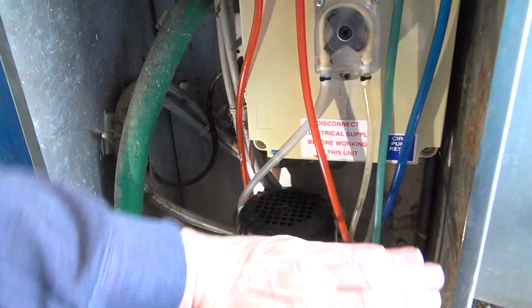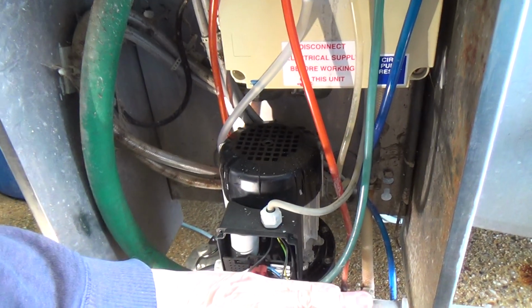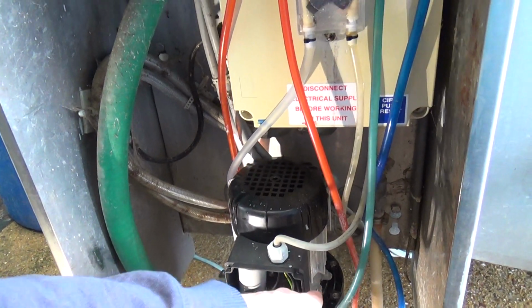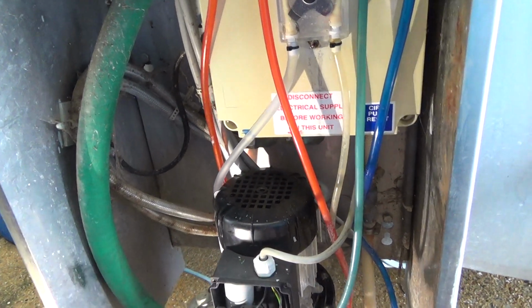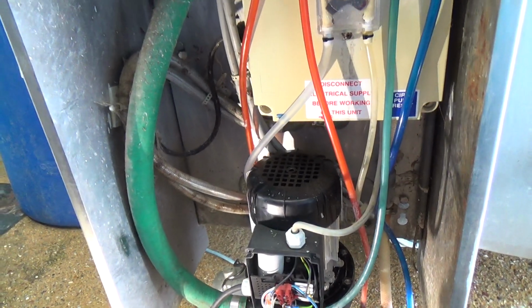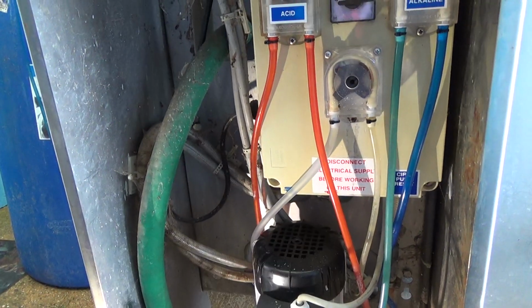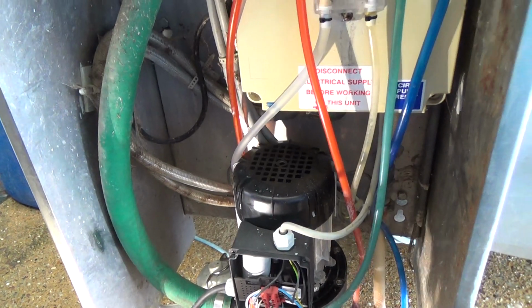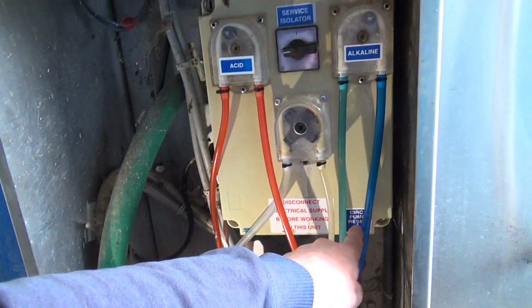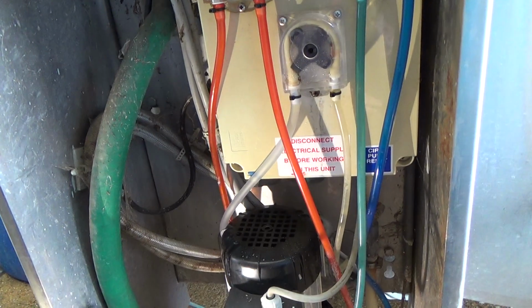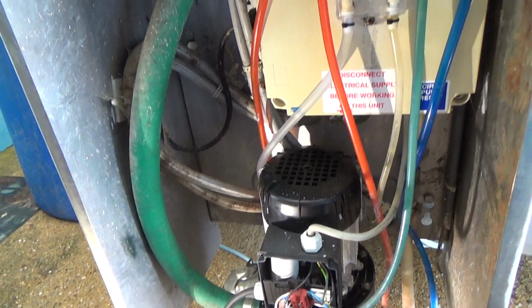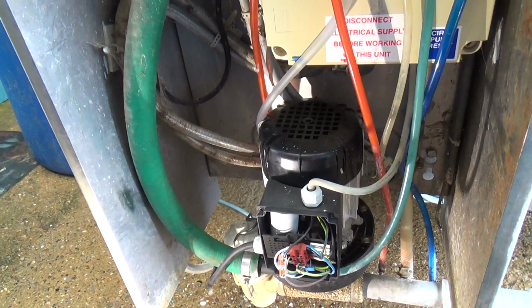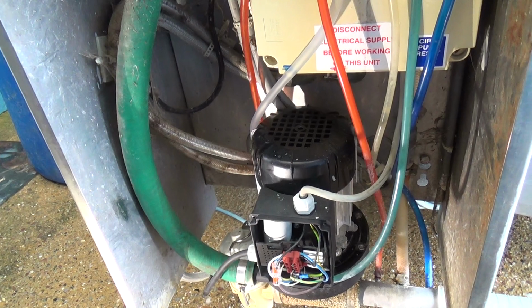The older ones, the pumps were horizontal. So in the winter time, there was always water left in the pump because they wouldn't fully drain. So winter time, tanker man comes on, puts the wash on, wash water's frozen in the pump and it'd burn the motor out. So they used to put these little trips on there, used to protect them a bit. But the vertical ones are just fully draining, so they don't really overly need it on there.